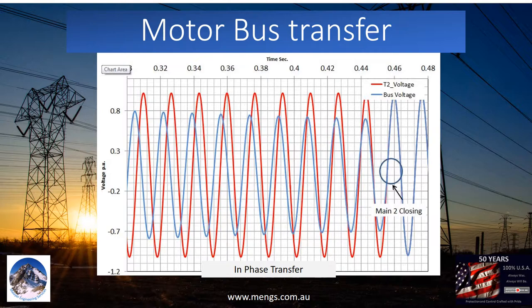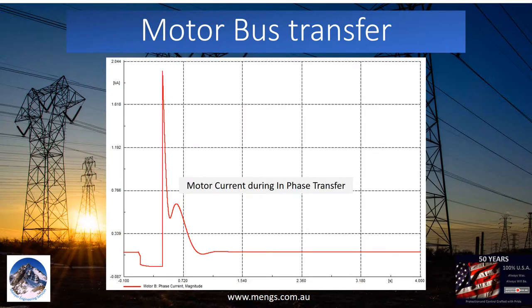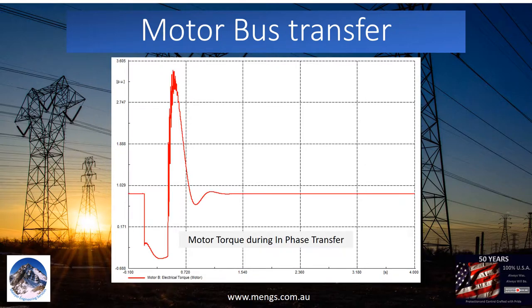In this slide, we can see how frequency difference generates phase angle difference. Since in-phase transfer happens within 10 to 50 cycles, the motor speed does not drop much. The transfer current in this type of transfer is between 1.5 to 3 times nominal current. Because in-phase transfer closes at the right angle, motors won't go to generating mode during transfer, and we will not observe large transfer transient torque.